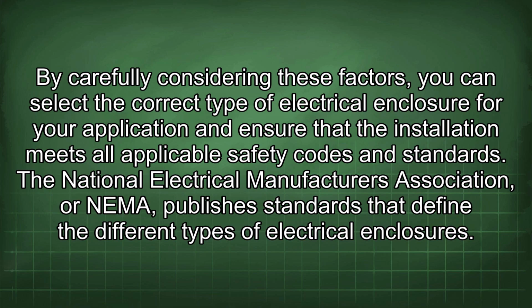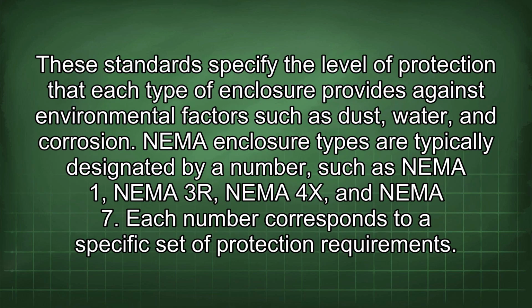The National Electrical Manufacturers Association, or NEMA, publishes standards that define the different types of electrical enclosures. These standards specify the level of protection that each type of enclosure provides against environmental factors such as dust, water, and corrosion. NEMA enclosure types are typically designated by a number, such as NEMA 1, NEMA 3R, NEMA 4X, and NEMA 7. Each number corresponds to a specific set of protection requirements.